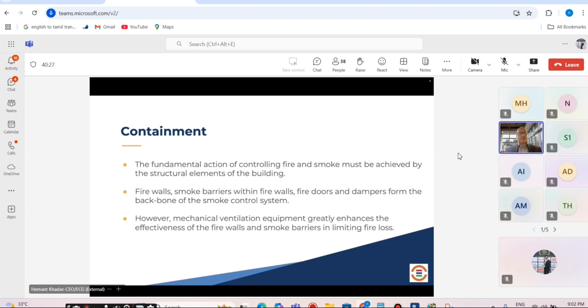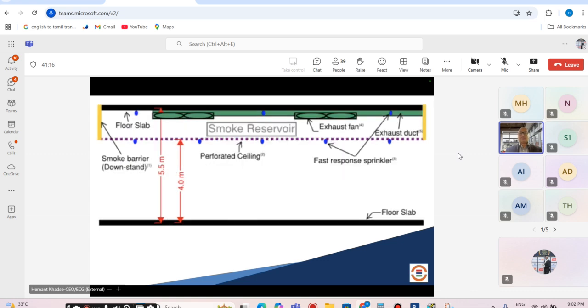These smoke zones, when you create them in that particular environment with fire dampers, are again part of a containment strategy. So when you design the systems, you also have to work with HVAC engineers to create those fire and smoke barriers. How is that integration going to be reflected in your cause and effect diagram? How is your fire alarm system going to behave in fire emergencies? What is the job of your smoke vent? What is the job of your fire dampers, and when are they going to activate? What's the rating of the damper? All these things have to be engineered.